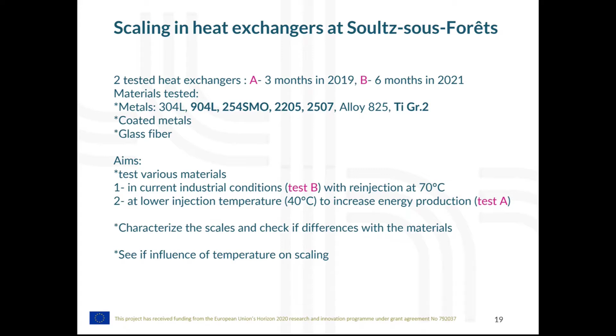So for test A, the design of the prototype heat exchanger is as follows. The inlet is on the top. The fluid goes from west to east with a first pass, written 1 on the lower figure. Then it goes to the east part of the exchanger, goes back in the intermediate.